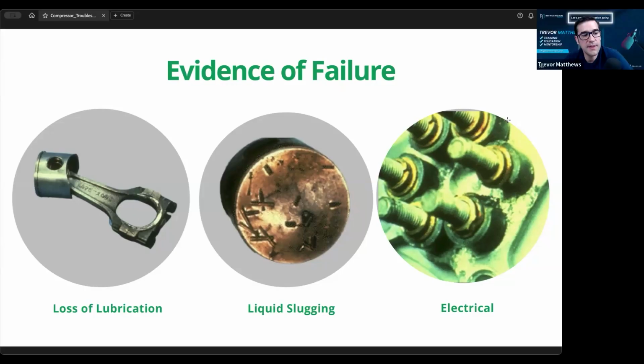Yeah. I think a big thing I've seen for electrical is people will go across the winding, and then it'll be like, oh, it's a shorted compressor. But actually, like you talked about earlier, it could be that contactor that is shorted, not the compressor. So this is why you always have to check it. If you get weird readings, because I've done it, you check it from the contactor first, and then it's perfect. You're always going to have a little bit more resistance than what the manufacturer says, because you're going through that wire, and there's resistance in the wire. But if you get weird readings, you have to go directly to that compressor. And even when you go directly to compressors, those insulators could be failed as well.